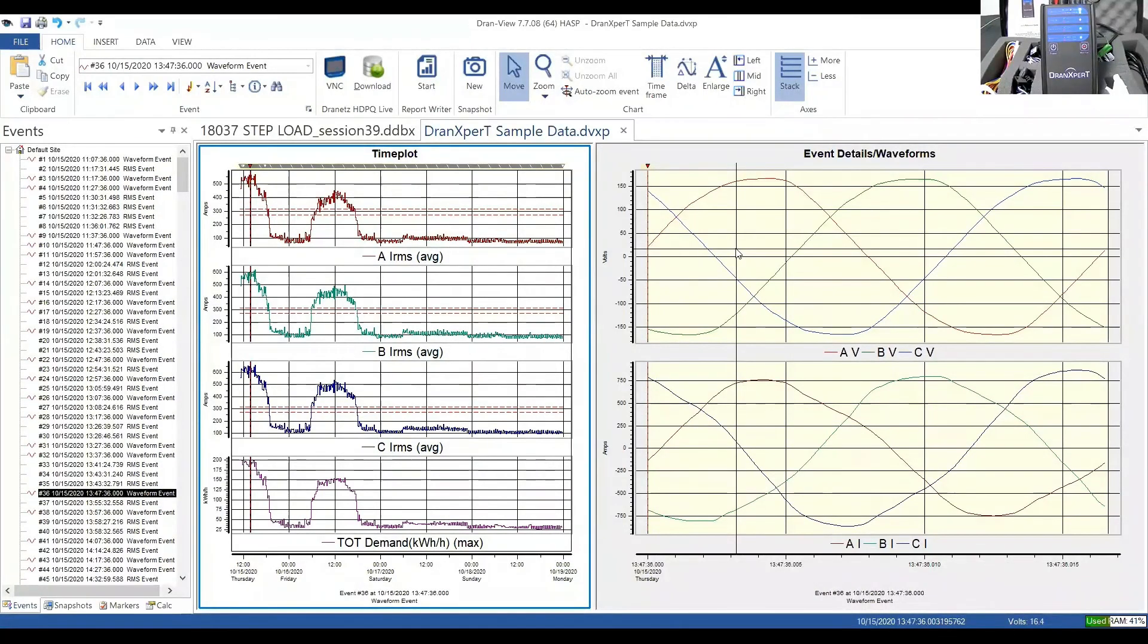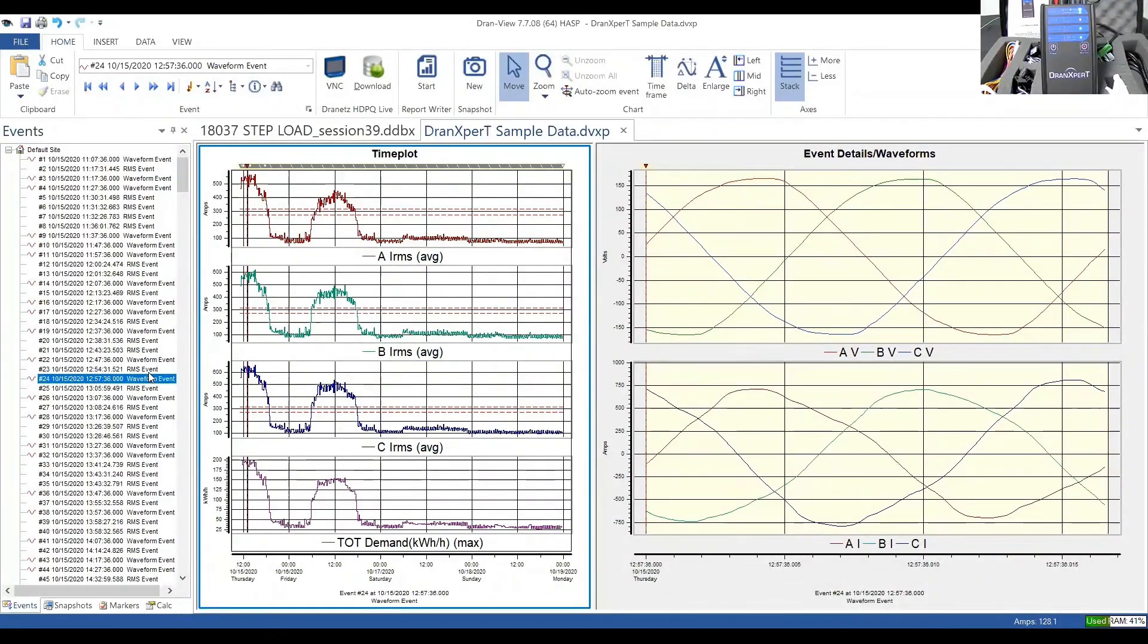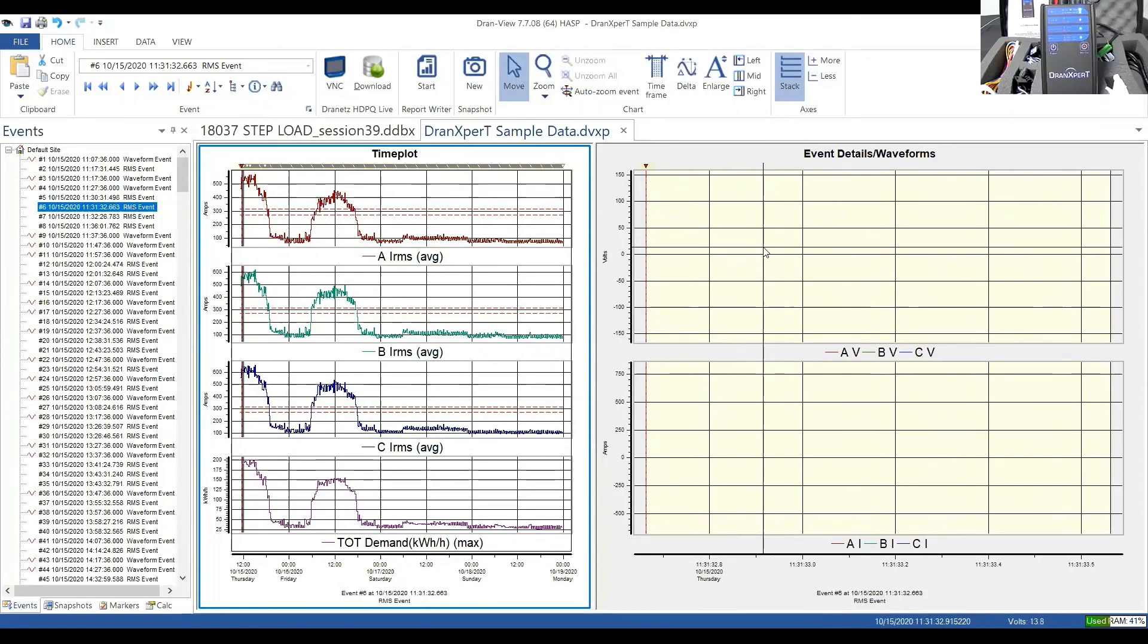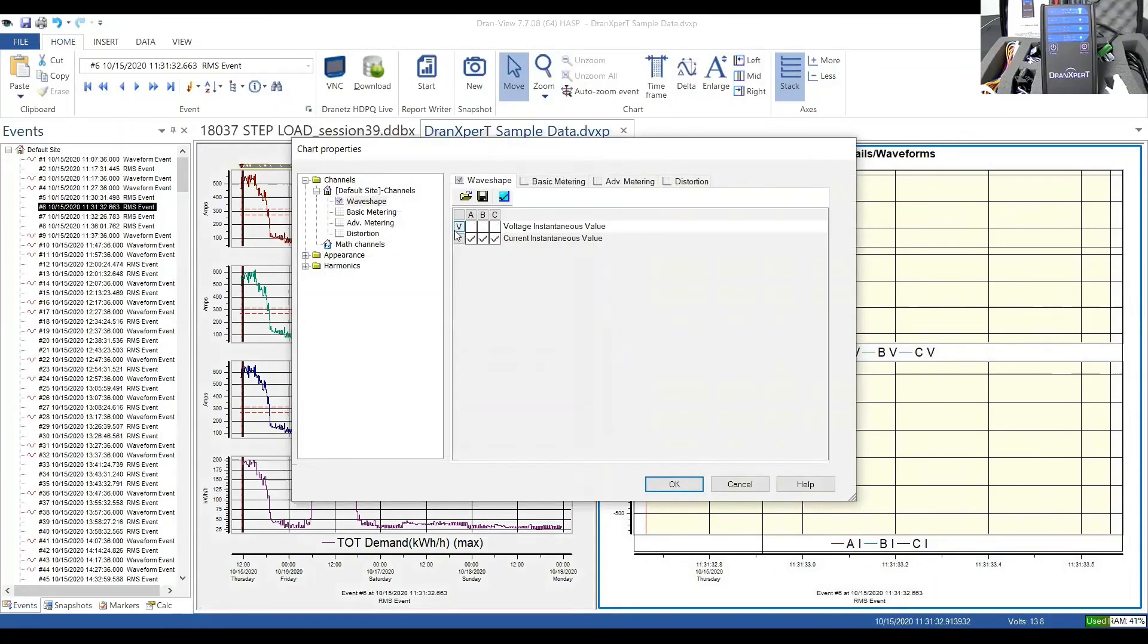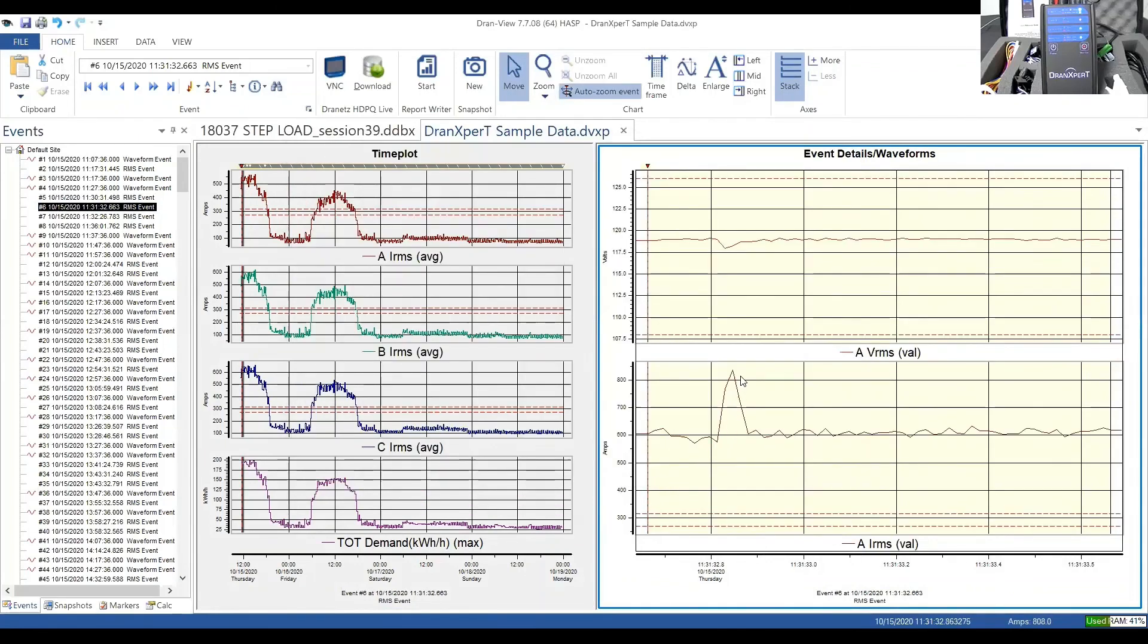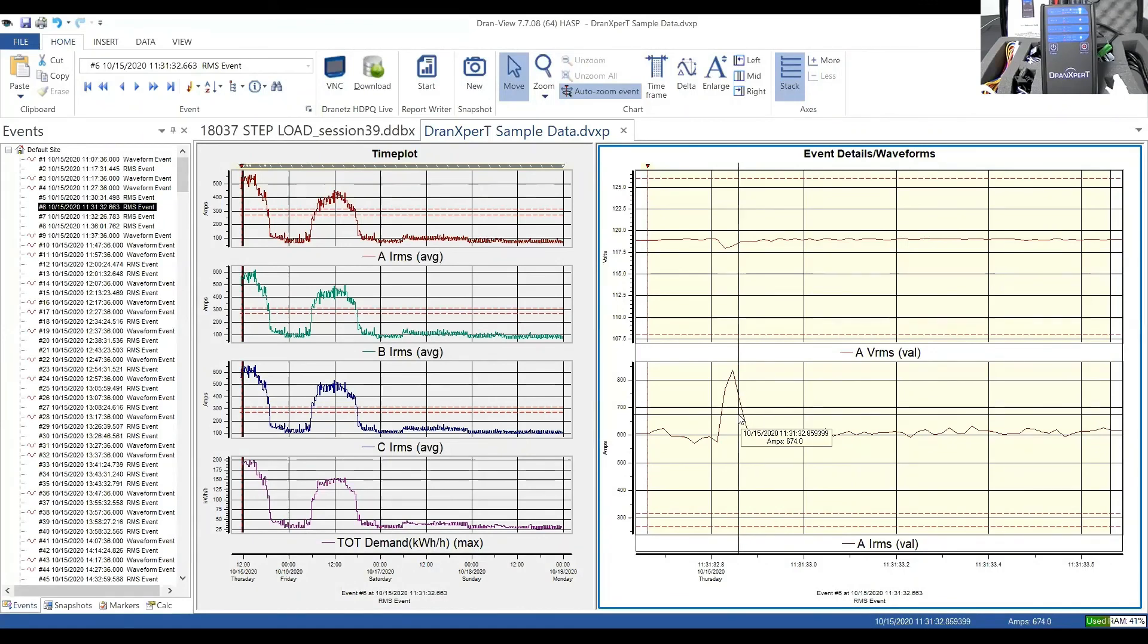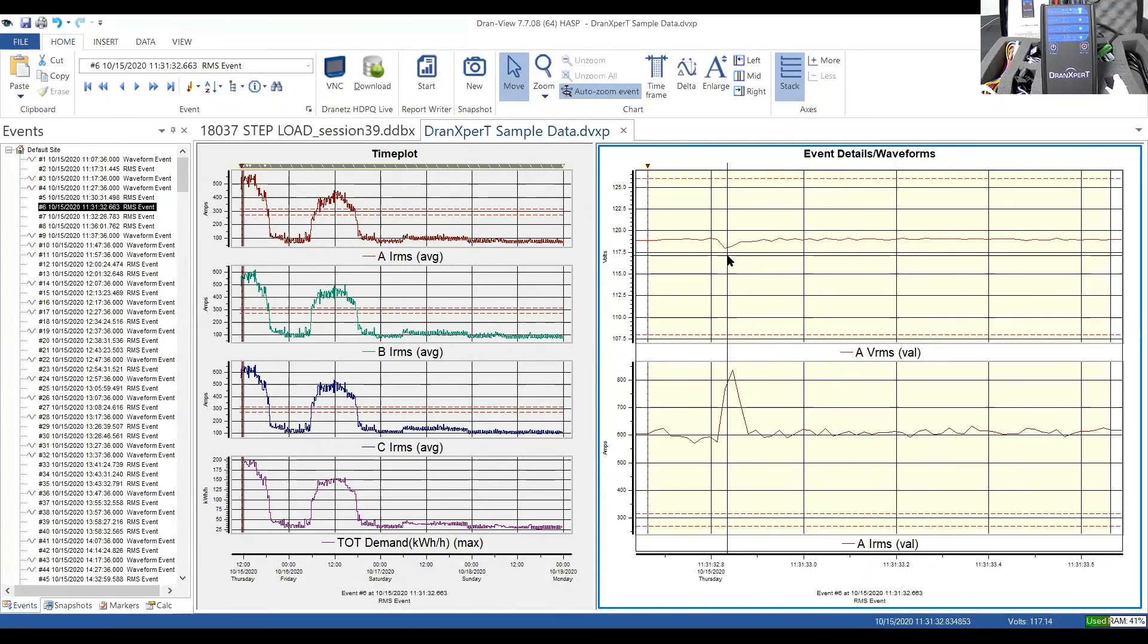So this is just our current loading and our energy for that survey or demand for that survey. We could see energy. Now on the right here, Thurman mentioned that you can record wave shape snapshots for the instrument. So I can see them recorded at a 10-minute interval in this file. I believe it's 10-minute interval. And you can see these wave shapes recorded. In addition, if you have an event, and there's a couple current trigger events here. Let me see if I can get it. In fact, I have to just change the properties here to look at the RMS of a waveform. So let me just look at voltage and current. And you can see them. These are current events that happen to be recorded because we set a fairly low current limit just for some tests. And you can see this is when the current exceeded the RMS threshold that Thurman was explaining. And this is a corresponding voltage at that time. I have just phase A here for voltage and current. And I can make any phase. I can do A, B, C as well and parallel them.